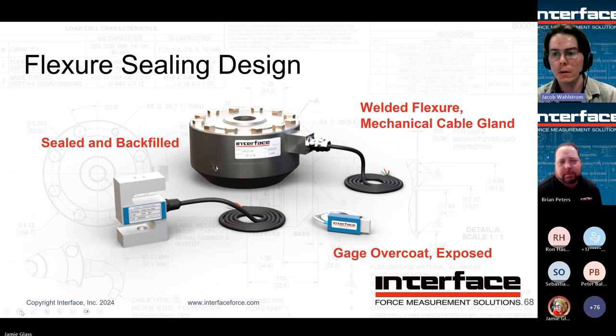You can see there in the middle, we have a welded, kind of hermetically sealed 3200. And so we've got the welded diaphragm, that's going to be top and bottom, as well as a welded, we call it a dog house, where we put a lot of the tabs and perhaps an amplifier. And then we have a cable gland coming out here with the cable.